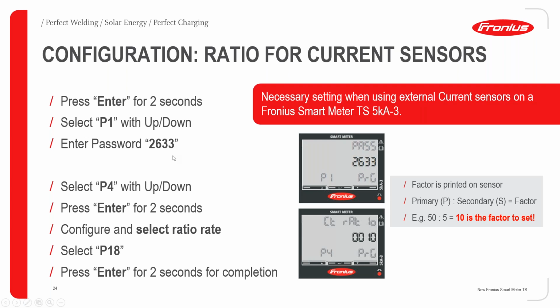And then you have to enter the password 2633 using the left and right up and down keys. Then as soon as you press enter for 2 seconds, you will say yes, confirm the password, and then you have to navigate to the menu P4. Here you have to enter the same way, press 2 seconds. Then in the menu P4, you have to select the ratio of the current sensors you have chosen to use. Then after entering the ratio, you have to go to the P18 menu, and then you have to press enter for 2 seconds for completion. So always P1 is like a password entering into the menu, and P18 is saving and exiting the programming menu.